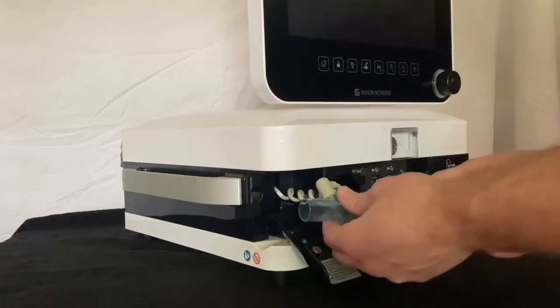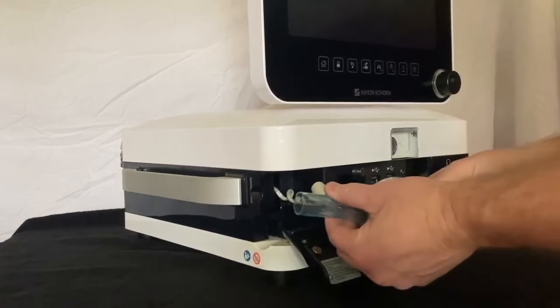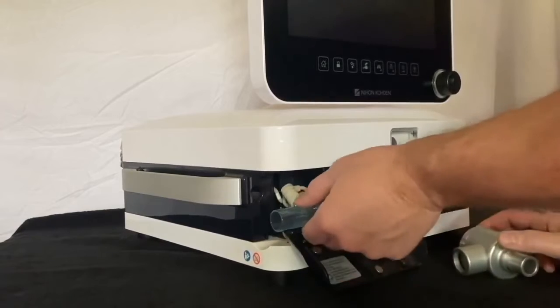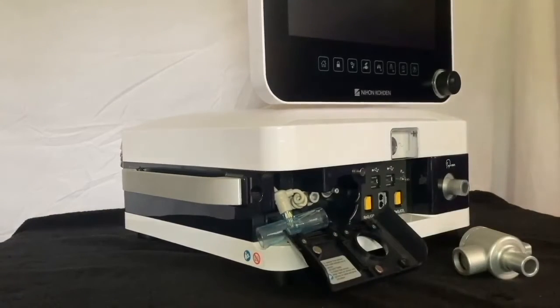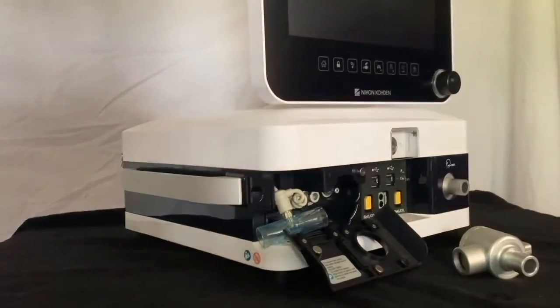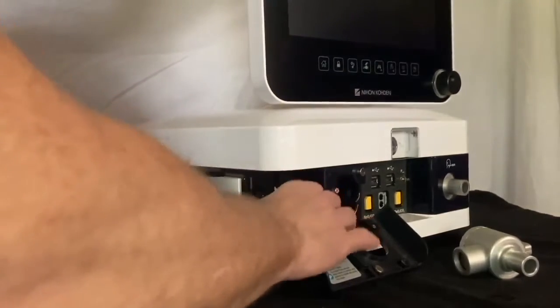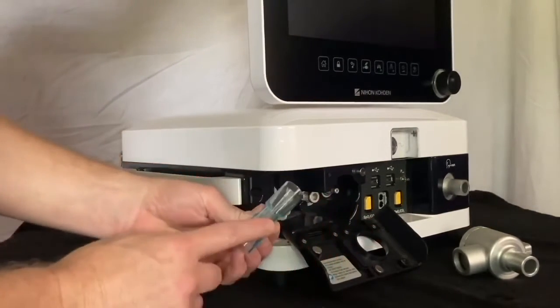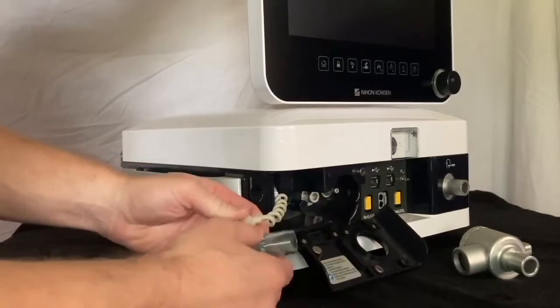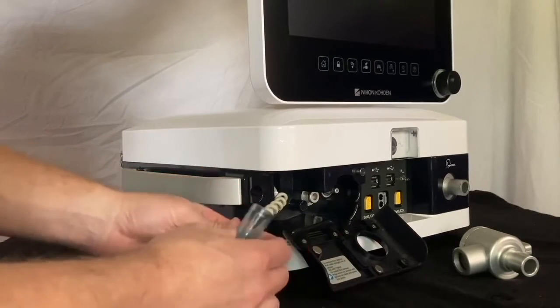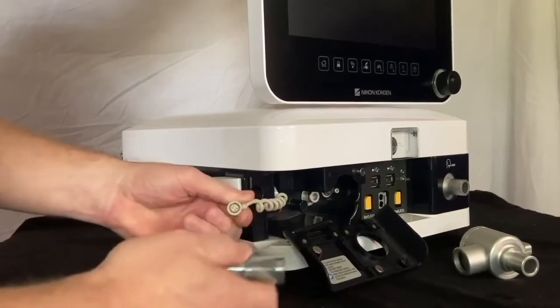To replace the exhalation flow sensor, grasp the exhalation flow sensor and pull outward to separate it from the exhalation valve assembly. And I want to pull the exhalation flow sensor cable straight out from the exhalation flow sensor without rotating or twisting. If I do, it's going to break the pins in there, the communication pins.